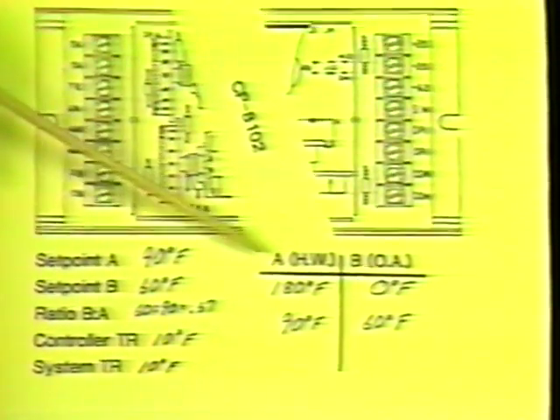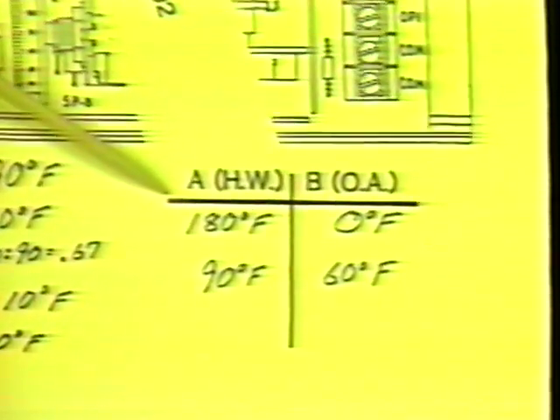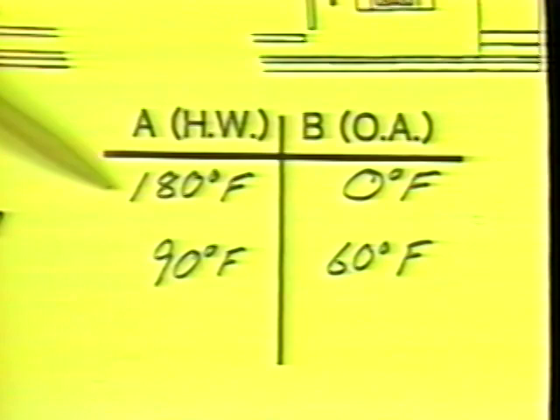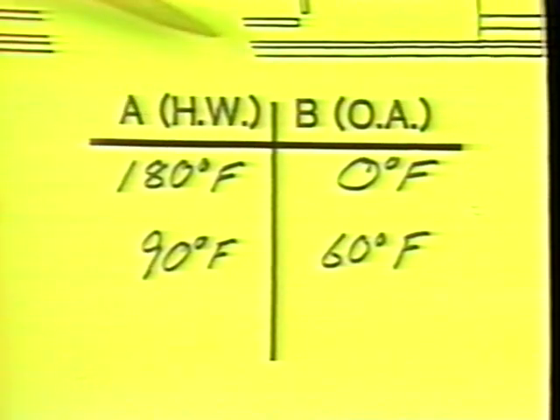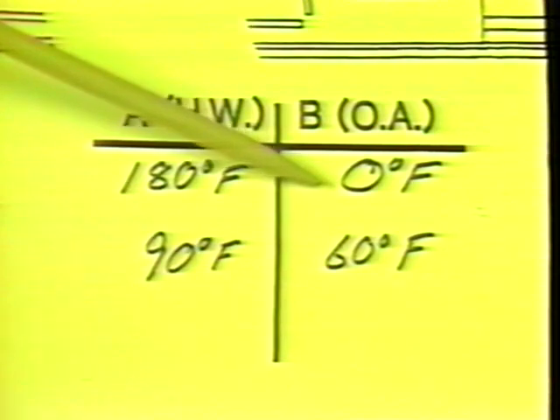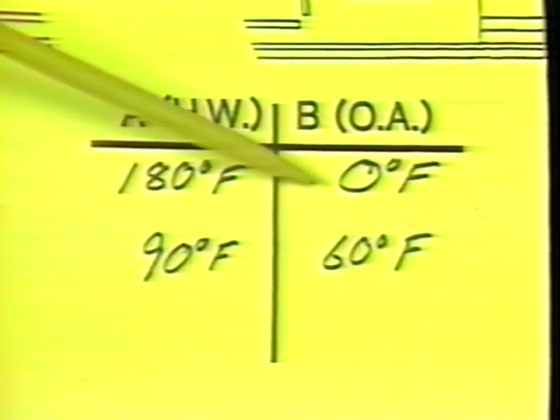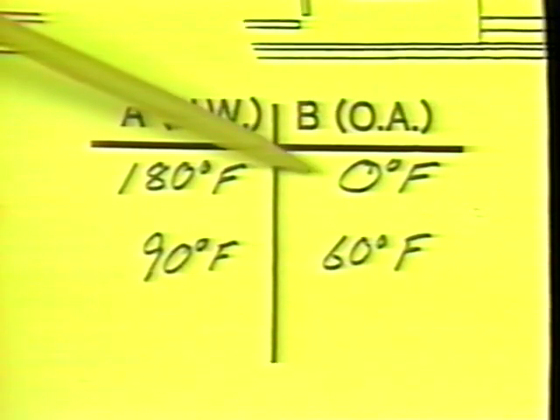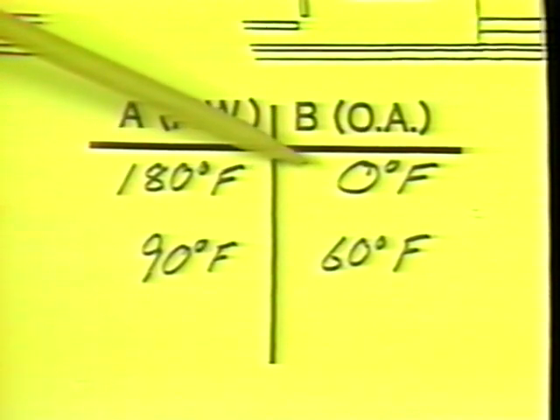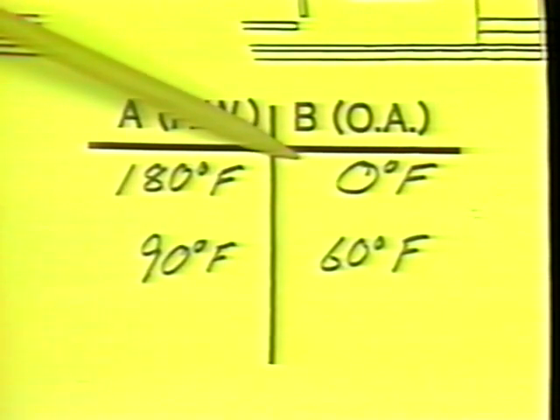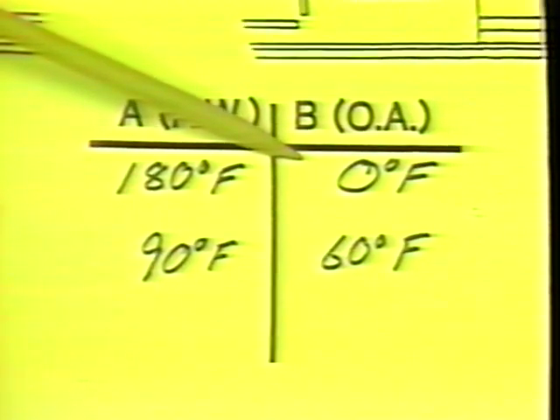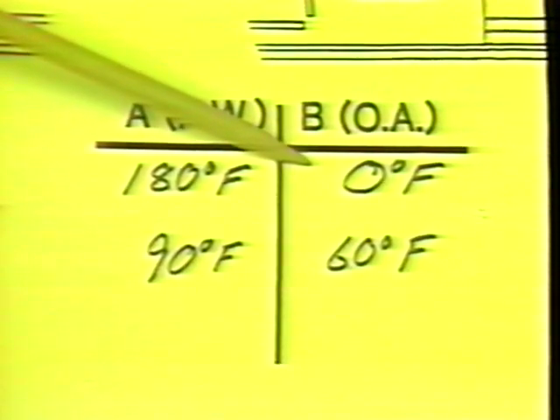We'll work out an example that will give us values for the controller settings. Let's say that the design engineer for a building has required that 180-degree Fahrenheit hot water be available when the outside air temperature is at its design temperature, or in this example, 0 degrees Fahrenheit. The design temperature is some low temperature, or if we're talking about cooling, some high temperature that is maintained over a period of time. It's not the absolute lowest or absolute highest temperature.